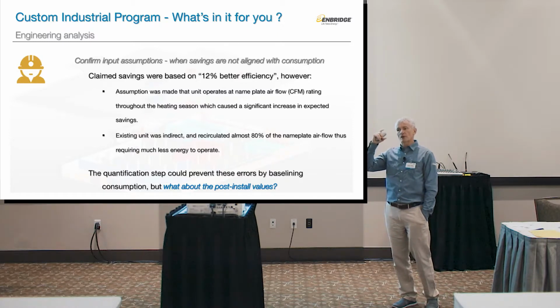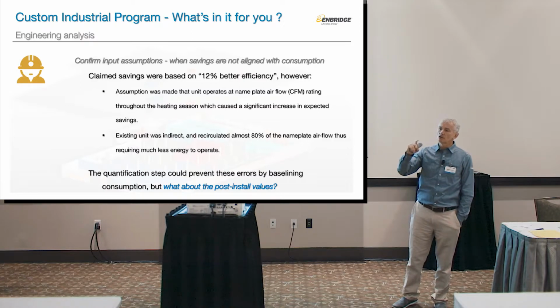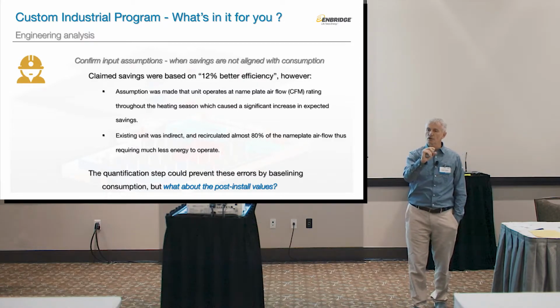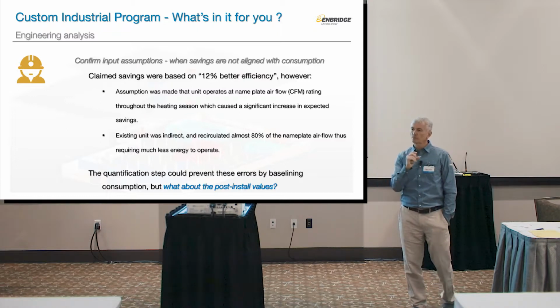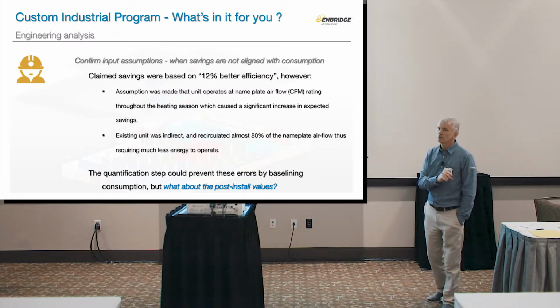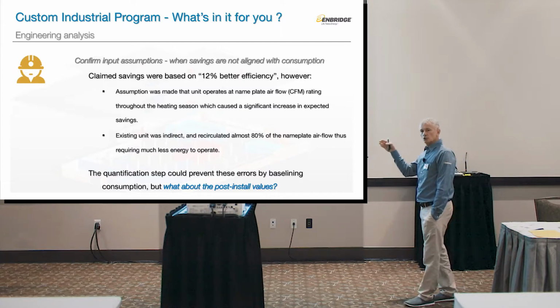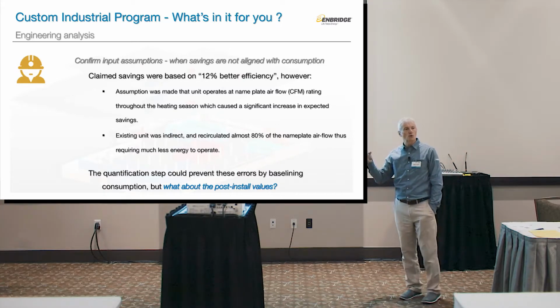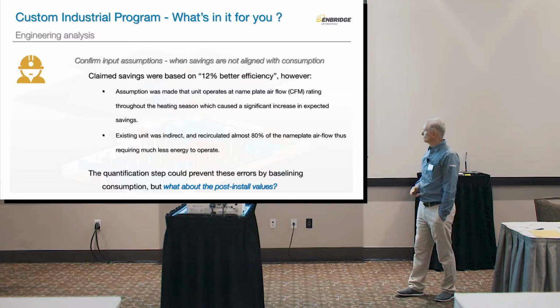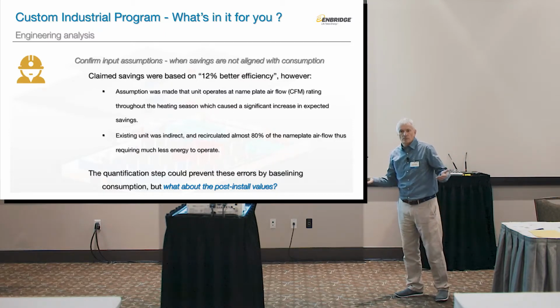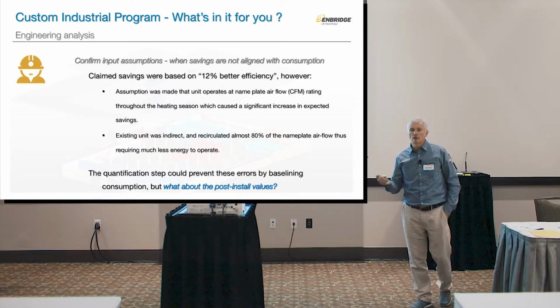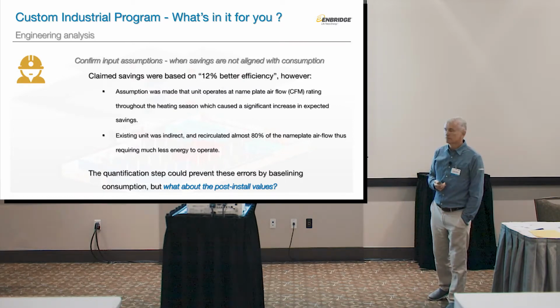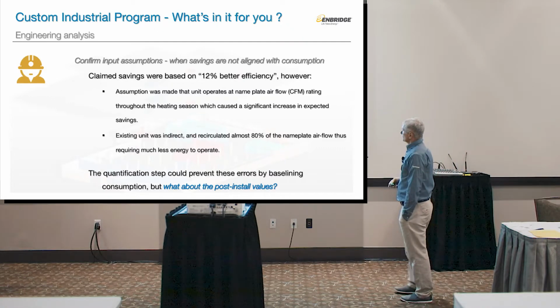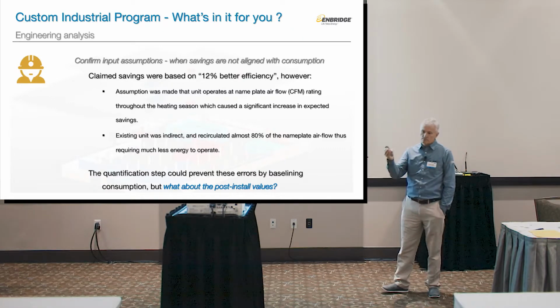So even if direct air heating is more efficient, you have to have 100% fresh air. Now 100% fresh air versus 20% fresh air is much more energy consumption than the 12% savings in the efficiency of the combustion. That would not have been caught if we didn't do the sanity check, if we didn't know what to compare it to. Because 12% looks legit. 92 versus 80, there's no question about that. But 12% of what? So we found that was done.